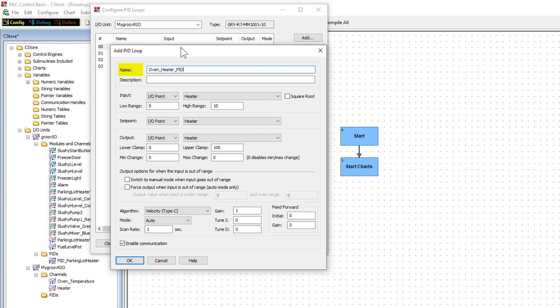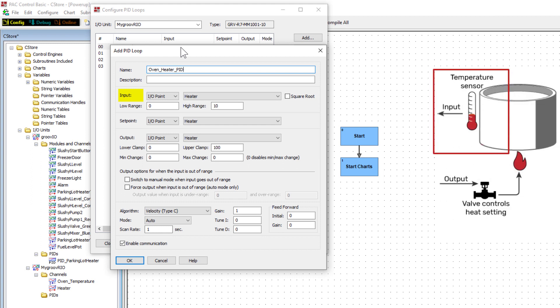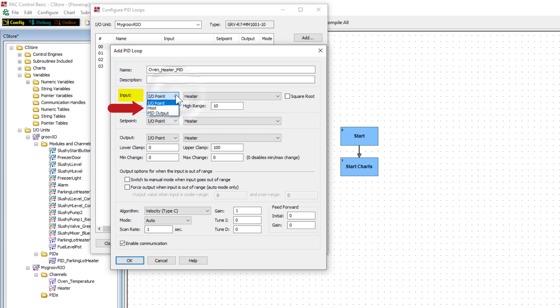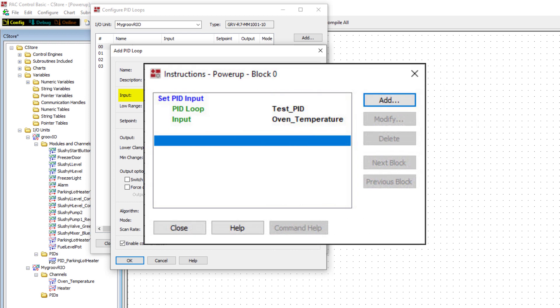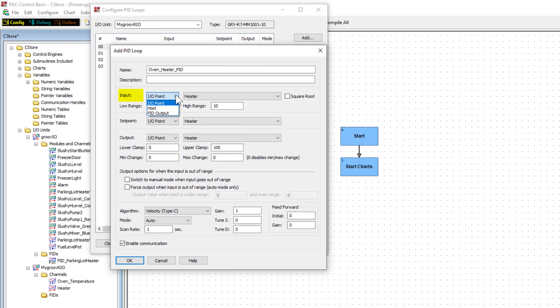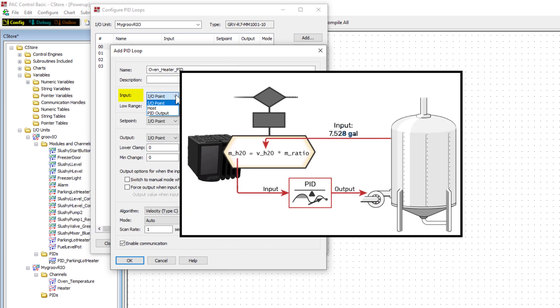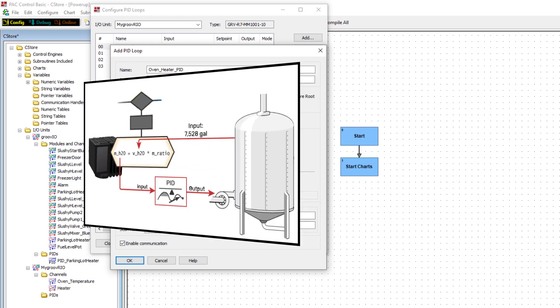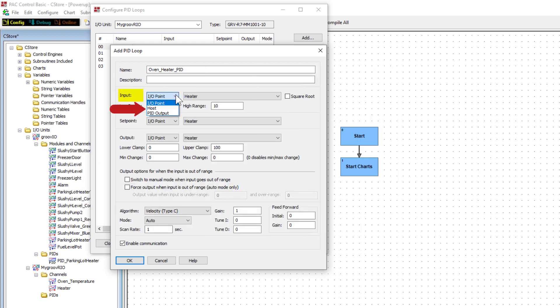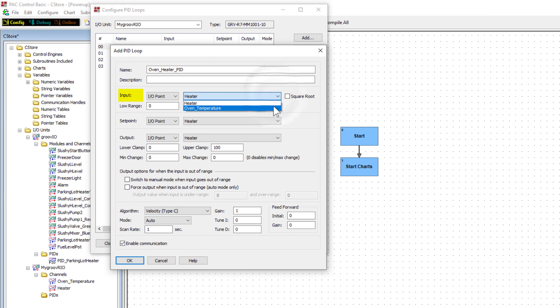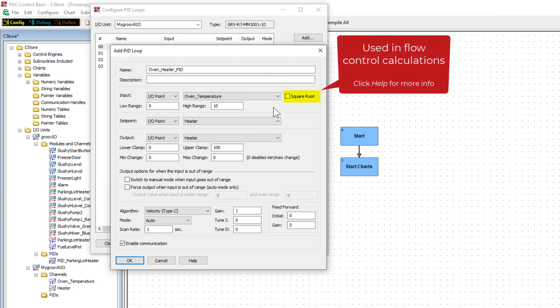The input is the process variable, the current value of the point you're monitoring. You can set the input to come in from an analog I.O. point that's configured on the I.O. unit, or have the input come in from host. This can be from PAC control, such as from the set PID input command, from a PID or input on another I.O. unit, or maybe even a process variable that needs to be modified in some way before it's fed into the PID. The input can also come from the output of another PID. This lets you set up a cascaded PID. One PID's results are fed into another. Choose I.O. point as the input and select the input point, oven temperature.